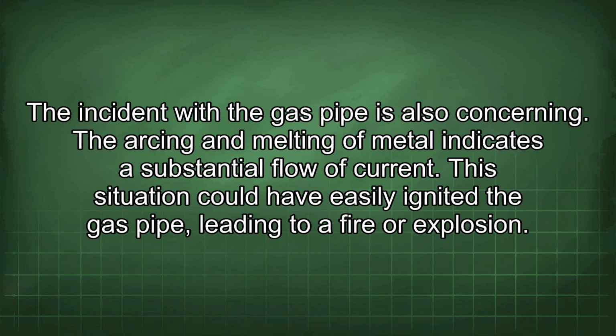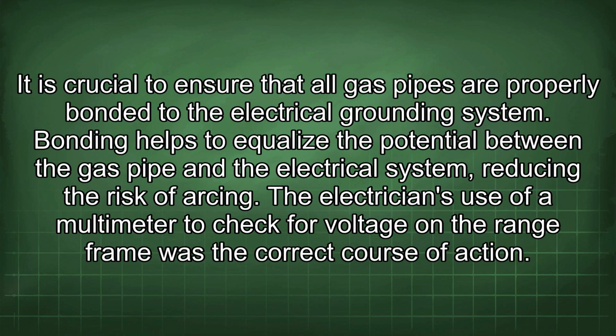The incident with the gas pipe is also concerning. The arcing and melting of metal indicates a substantial flow of current. This situation could have easily ignited the gas pipe, leading to a fire or explosion. It is crucial to ensure that all gas pipes are properly bonded to the electrical grounding system. Bonding helps to equalize the potential between the gas pipe and the electrical system, reducing the risk of arcing.